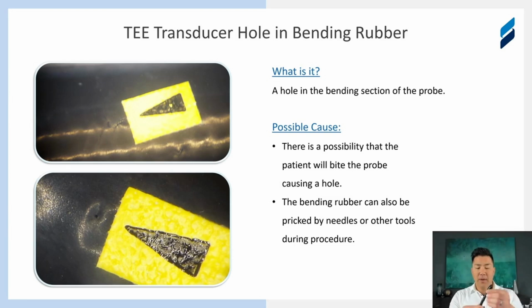And what's important here is that these can falsely pass a leakage test. The reason being is that if you actually bend and articulate this transducer forward, if the hole was on the front of this where it's bending, it would now be closed, right?